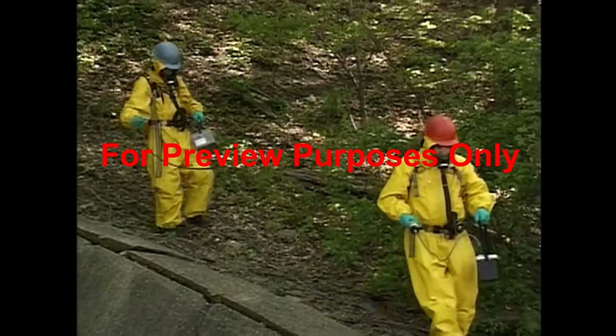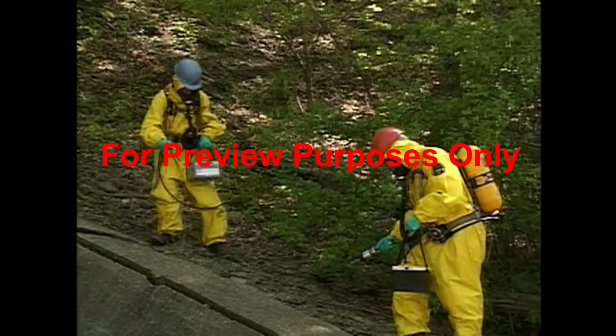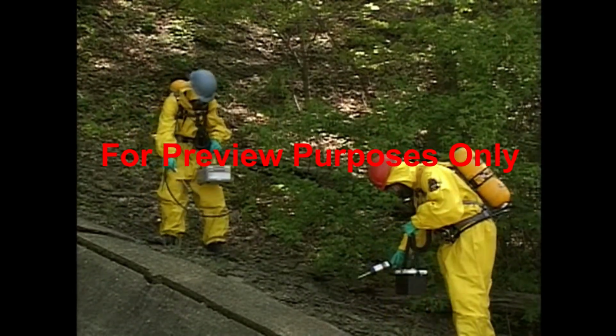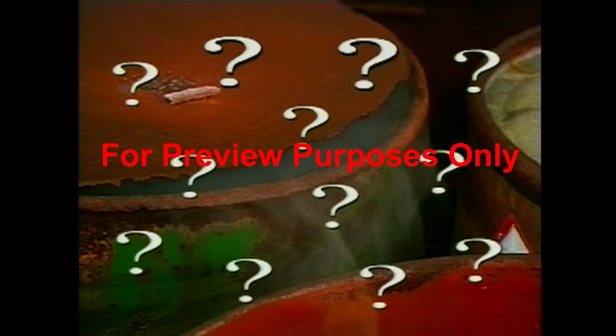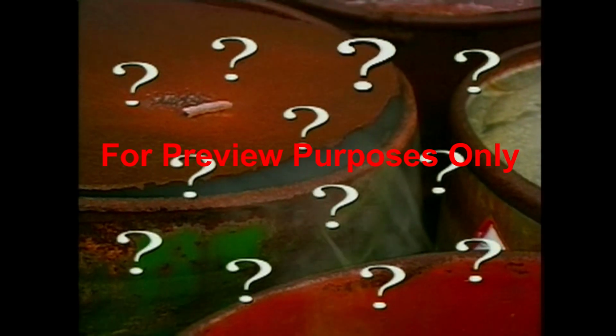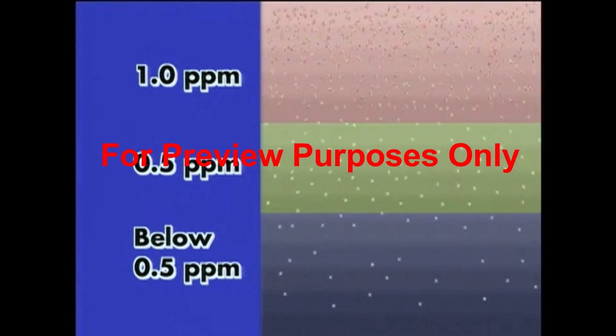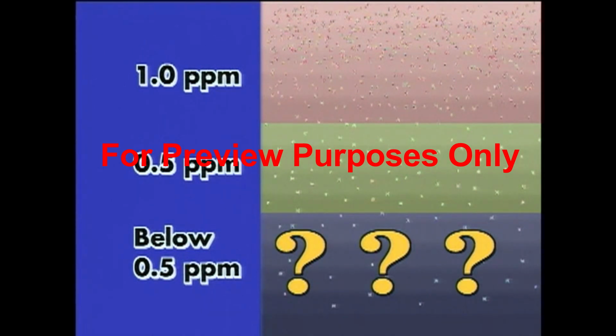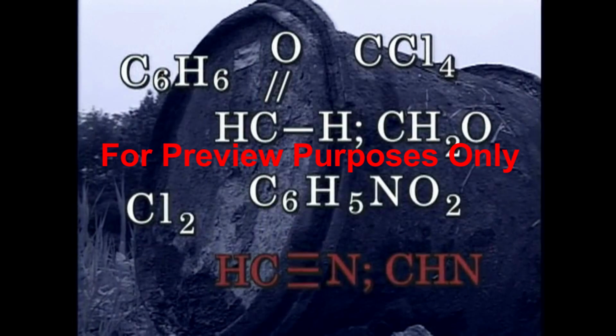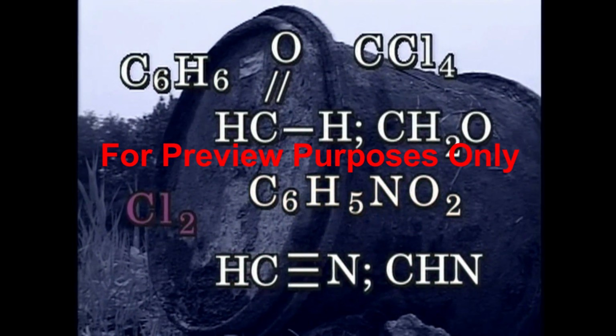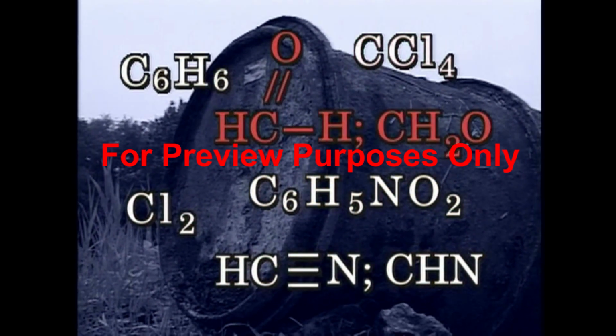Direct reading instruments do have weaknesses, though. For instance, each one is sensitive to only a limited range of chemicals. There is no single direct reading device that picks up every contaminant. Even highly sensitive direct reading instruments cannot detect concentrations below 1/2 of 1 part per million. But certain chemicals are hazardous in quantities below this level, where a direct reading device will not be able to pick them up. And where multiple chemicals are present, direct reading instruments may not be able to distinguish between them.